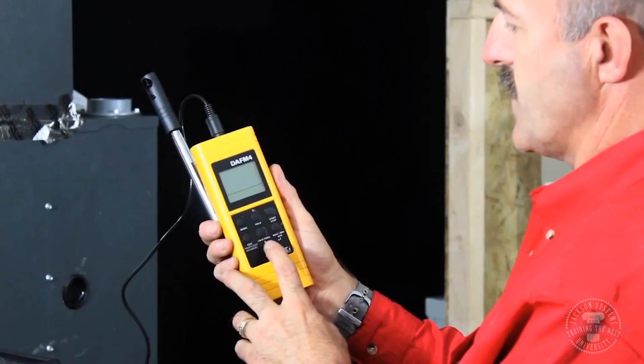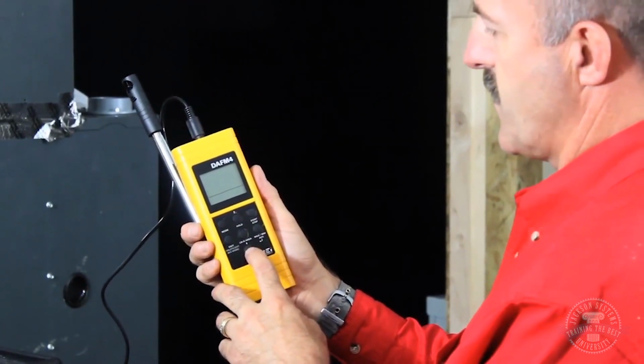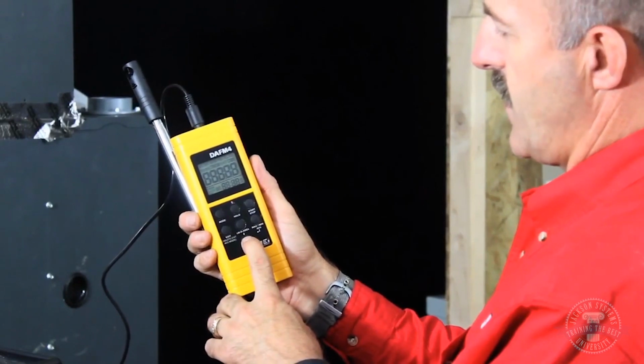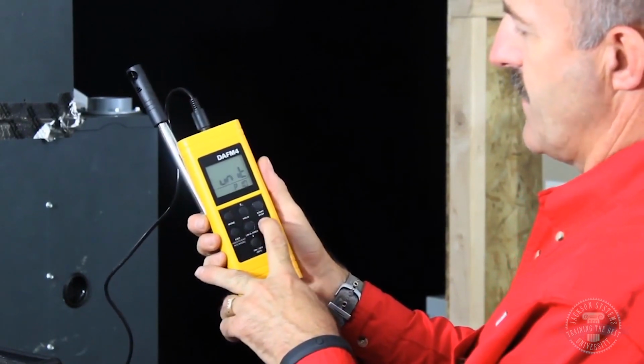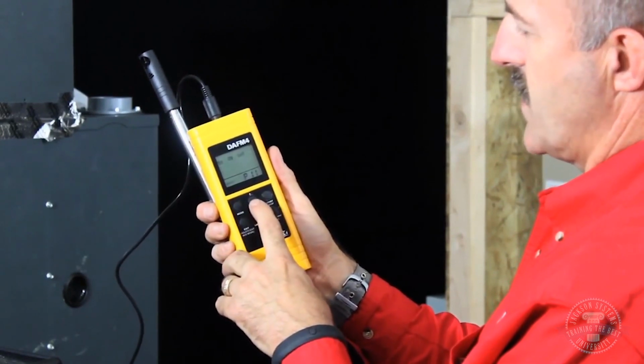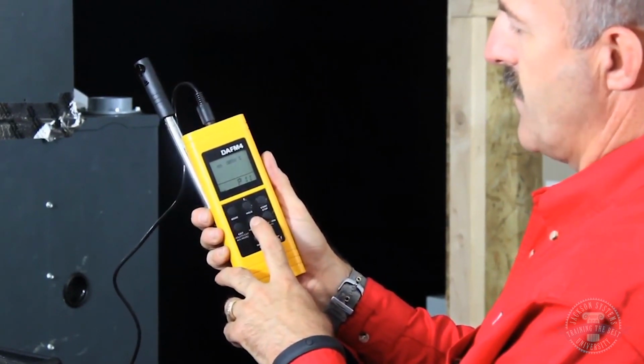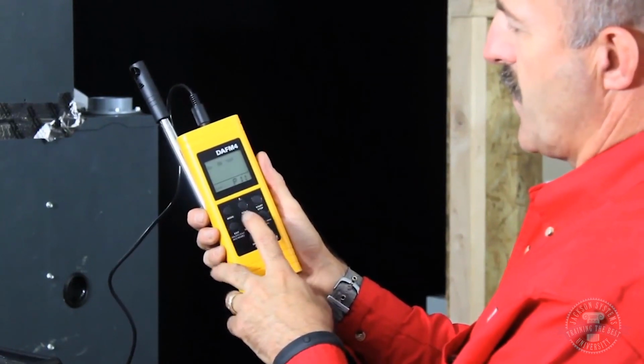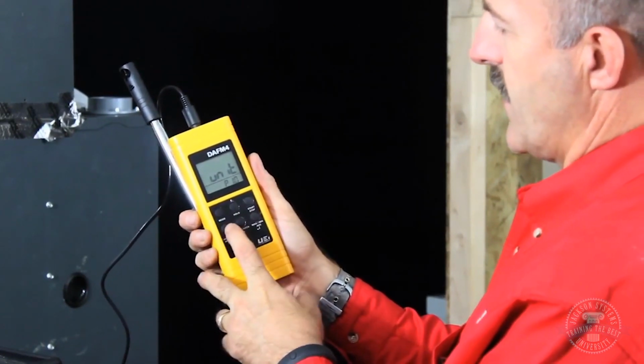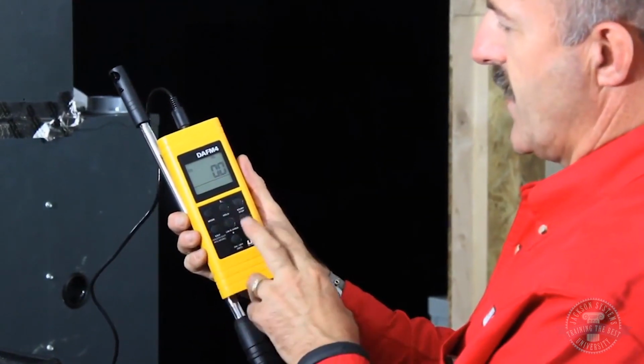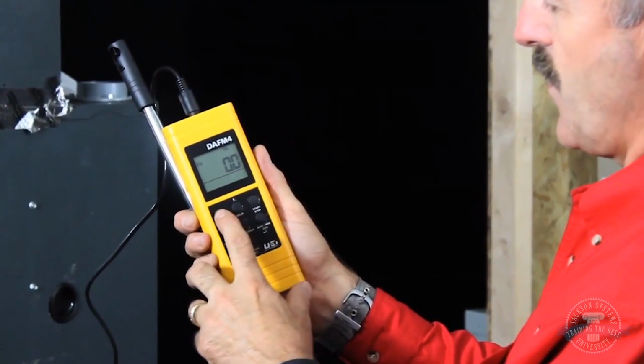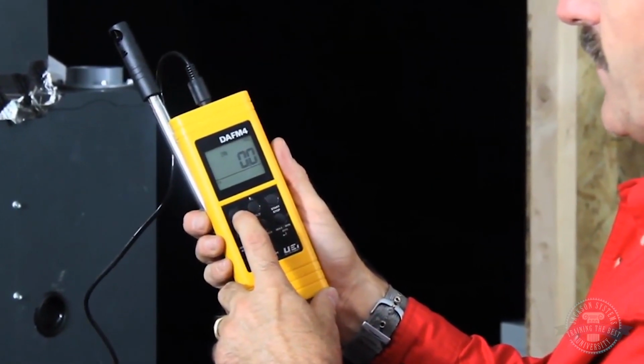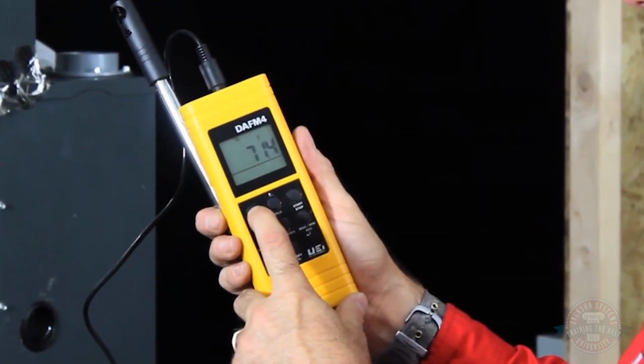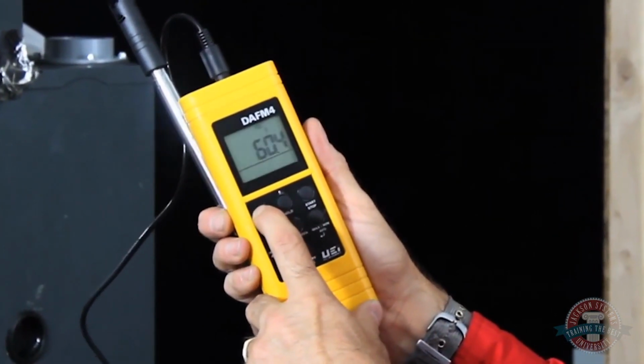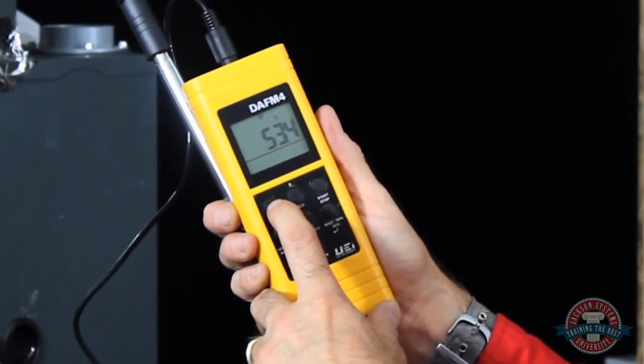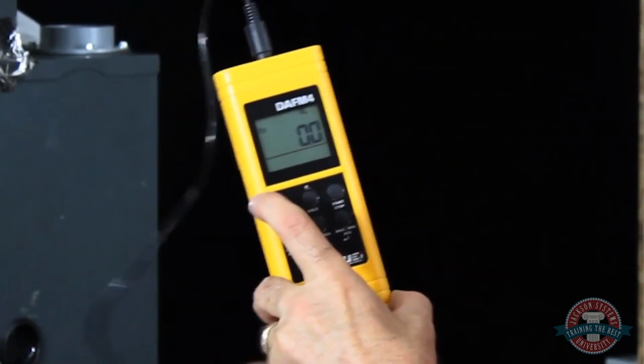The first thing before we use it is I want to set the units to standard instead of metric. So I press and hold the on-off until the units option, then hit enter, and you can use up or down to change between Fahrenheit and centigrade, or standard and metric. I'll put it in degrees Fahrenheit, hit enter, and then exit takes you to normal mode. In normal mode you have velocity, and you scroll through by pressing mode: volume, I'll come back to that, ambient temperature, relative humidity, wet bulb temperature, and dew point. I go back to velocity, and that's just a direct read.